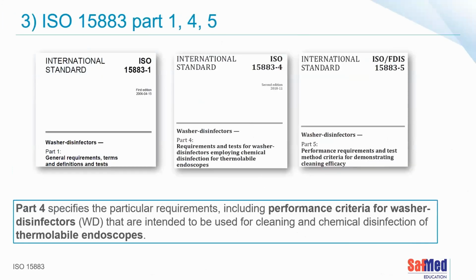I'm sure a lot of you are familiar with ISO 15883, the manufacturing standard that covers washer disinfectors. Part one covers the general requirements for all makes and models of washer disinfectors. Part 4 is specific to endoscope washer disinfectors, and Part 5 covers the test methods we use to demonstrate the cleaning efficacy of a washer disinfector.